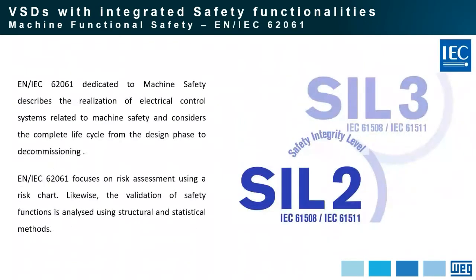So checking the part of this standard that is related to machine safety, it describes the realization of electrical control systems related to machine safety and considers the complete life cycle from the design phase to the decommissioning. It also focuses on risk assessment using a risk chart. Likewise, the validation of safety functions is analyzed using structural and statistical methods.